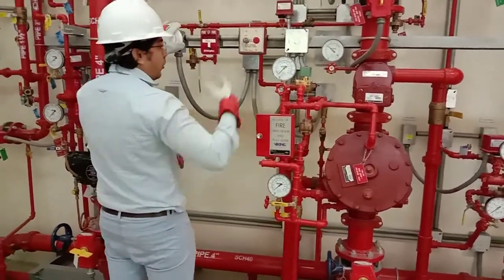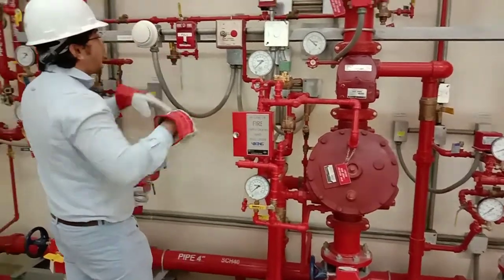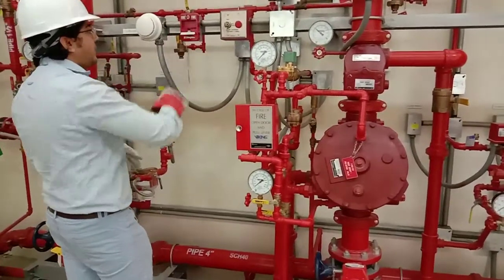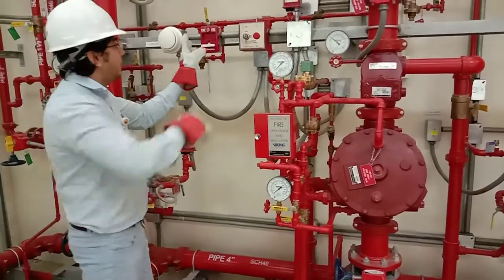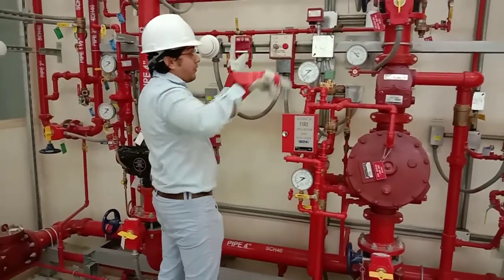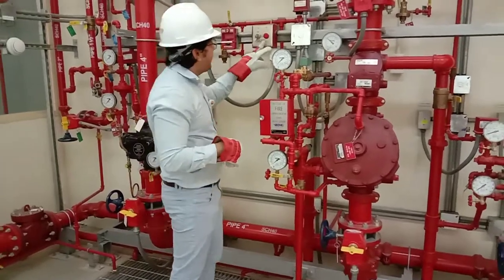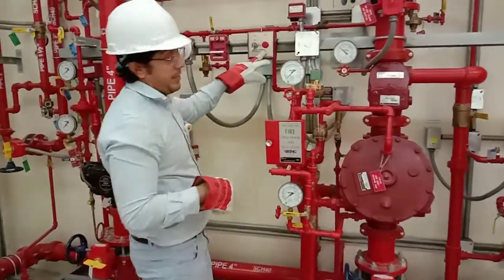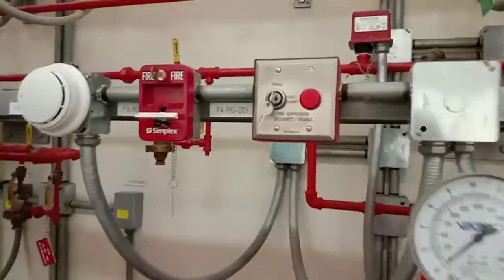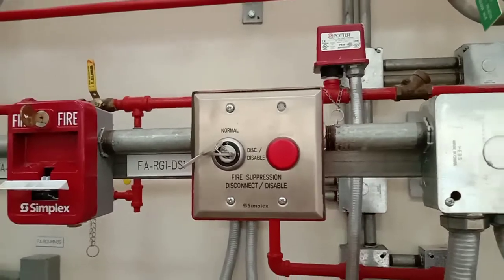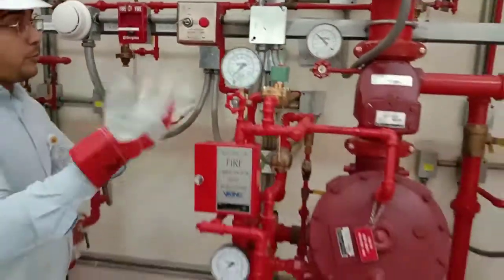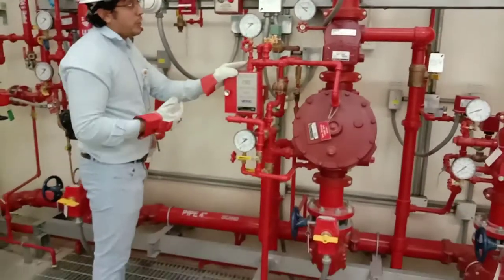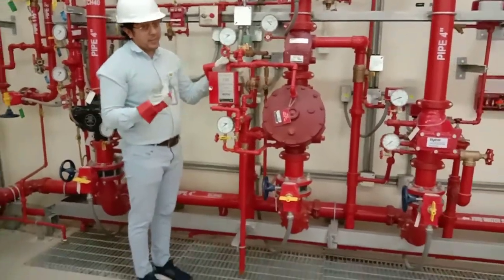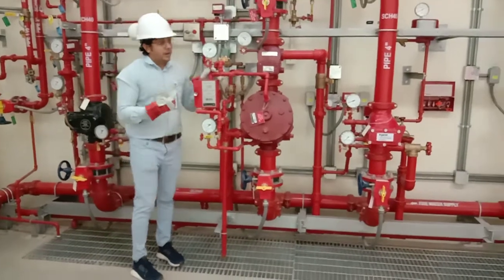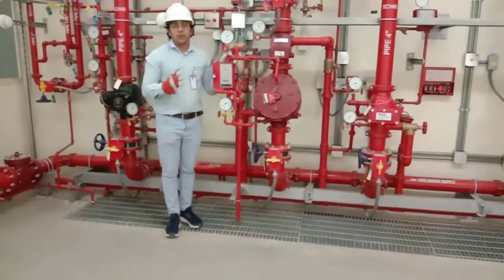So this one is a detector for the pre-action system. Here we have again a pull-down option, right, so that we can activate it manually in case of fire if we are present nearby the fire areas. And again we have a fire suppression disable or disconnect system. It means if you want to maintain the system, we just turn the system to this one, like it is in disable condition, and then you do the maintenance. If you want to do some maintenance, disable first prior to going to maintenance. Again, I will emphasize this item that this kind of system should be maintained by a qualified contractor.